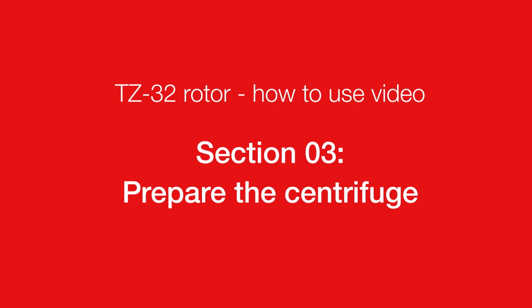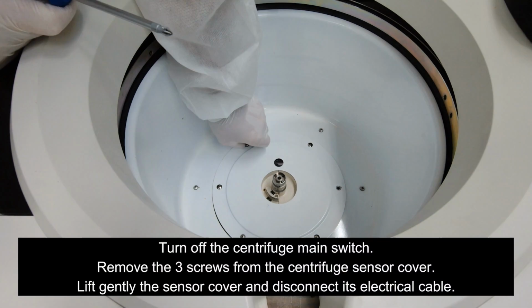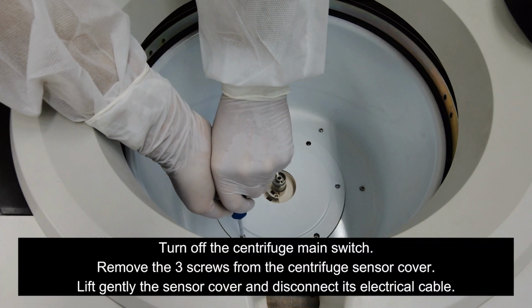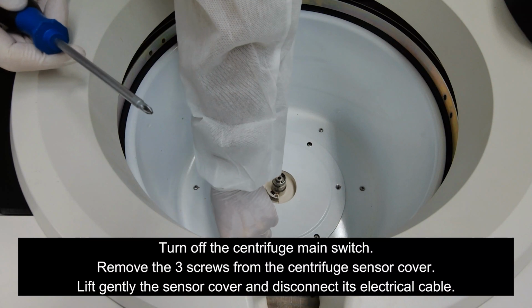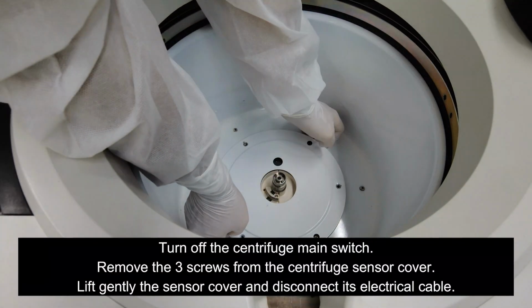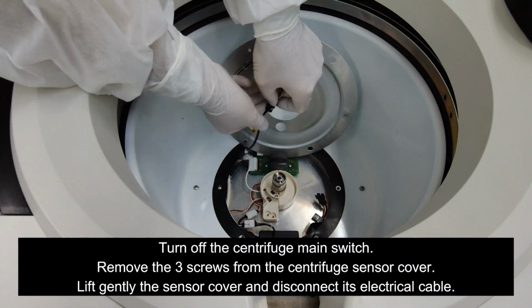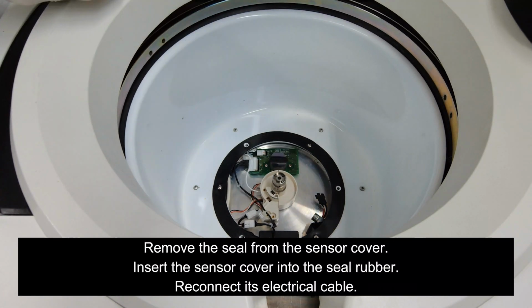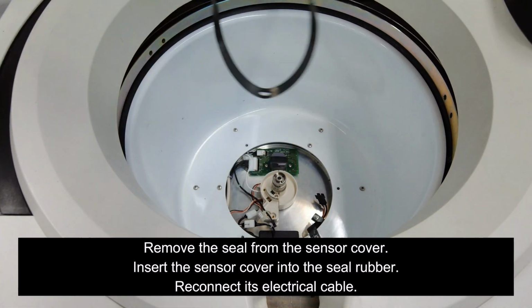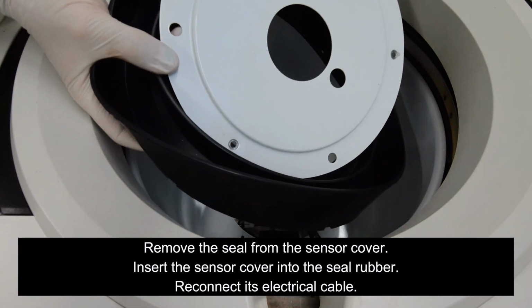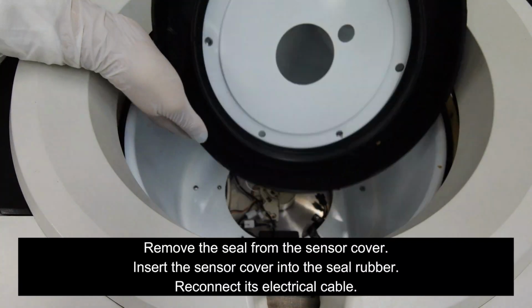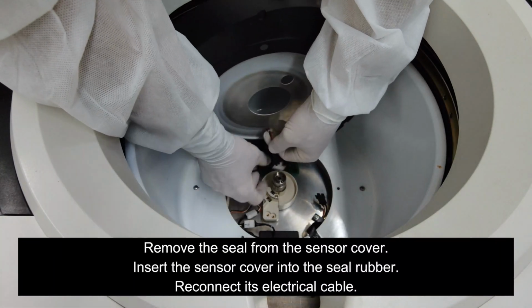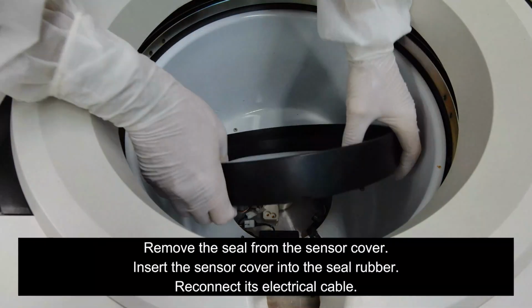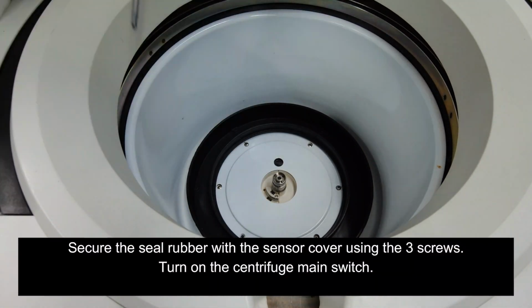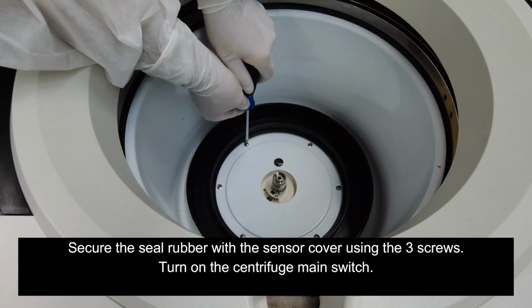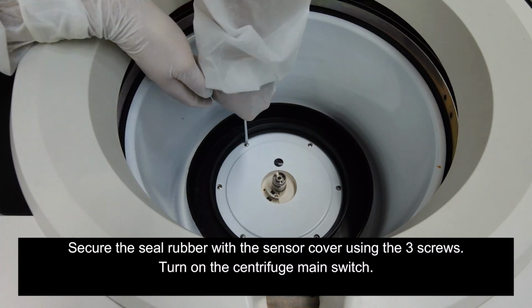How to use video. Section 3. Prepare the centrifuge. Turn off the centrifuge main switch. Remove the 3 screws from the centrifuge sensor cover. Lift gently the sensor cover and disconnect its electrical cable. Remove the seal from the sensor cover. Insert the sensor cover into the seal rubber. Reconnect its electrical cable. Secure the seal rubber with the sensor cover using the 3 screws. Turn on the centrifuge main switch.